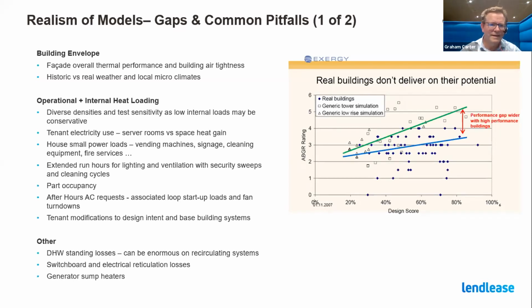In terms of tenant and heat loading assumptions, it's really important that diverse densities are used — the more homogeneous a simulation is with internal load assumptions and hours, the more optimistic and less realistic it becomes, so it's important those are varied. I also think low internal loads in the UK are probably a more NABERS-conservative position. This brings me to the next point: we often input equipment loads representative of total tenant equipment electricity use, but we need to keep in mind that about half of that power use is in server rooms, which typically doesn't represent a heat gain on base building air conditioning systems. So 7-8 watts per square meter of equipment load in modern office buildings is quite enough.